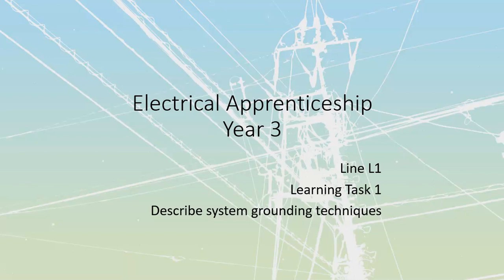But underneath that, we've got another 2 bullet points that talk about how these systems differ from the single-phase systems that you've looked at before. One of the major differences is we are sometimes going to have tiny values of fault current. Very small, and it's going to be very controlled, instead of a large value of unrestricted current the way that we do on single-phase grounding. And the other difference is that our overcurrent device will not always automatically trip to de-energize the system. In some cases, the system's going to stay energized, either for a specific amount of time or indefinitely, and there's just going to be a warning placed so that qualified electricians are going to understand what's going on.